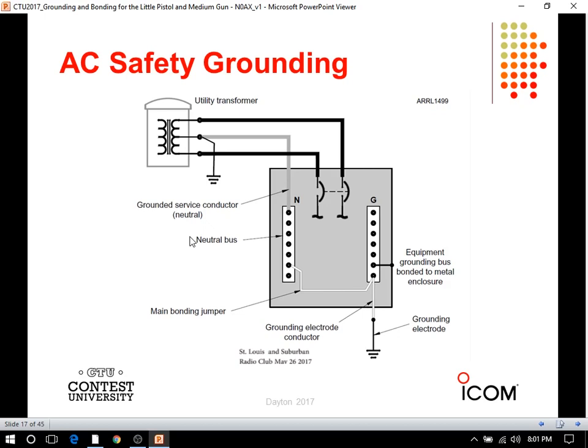When did they put that ground to the outside? When did that start? Is that a newer thing, or does a house that's built in the 30s have that? If you go downstairs or wherever your circuit breaker box is, find the big wire coming off your grounding bus, and follow it. It'll go outside through the wall, and it should go directly to a ground rod right outside.